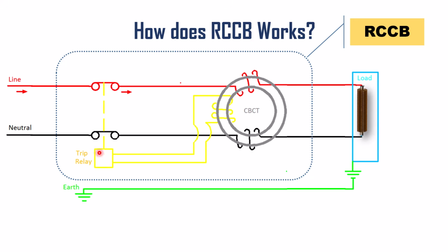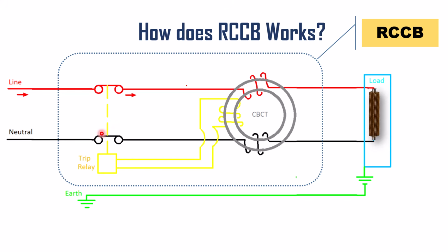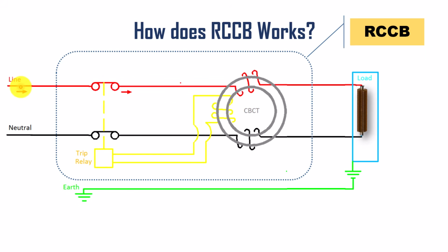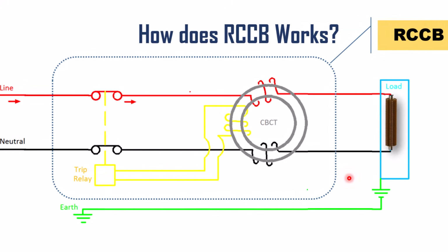Let's try to understand how RCCB works. This is the internal structure of the RCCB. These are the internal electrical contacts. This is a CT, which is CBCT or core balance CT. Both the phase and the neutral conductors pass through this CT. The secondary of this CT is connected to the trip circuit, which ultimately opens these electrical contacts. And these are the phase and the neutral coming from the MCB, and the output of RCCB is directly connected to the load.